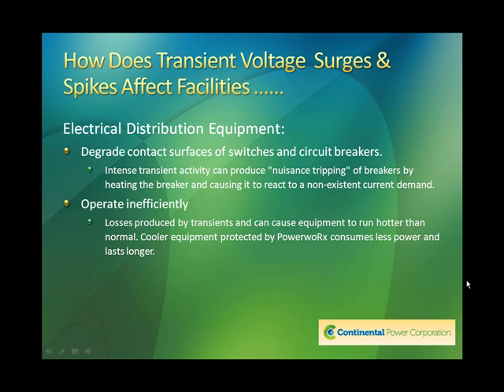Electrical distribution equipment. Most people don't think about this, but surges degrade the contact surfaces of switches and circuit breakers. Nuisance tripping can be attributable to transient activity. Breakers heat up and they actually react to a non-existent current demand. Operational inefficiency: losses produced by transients can cause equipment to run hotter than normal, in the same way that we've talked about with motors.